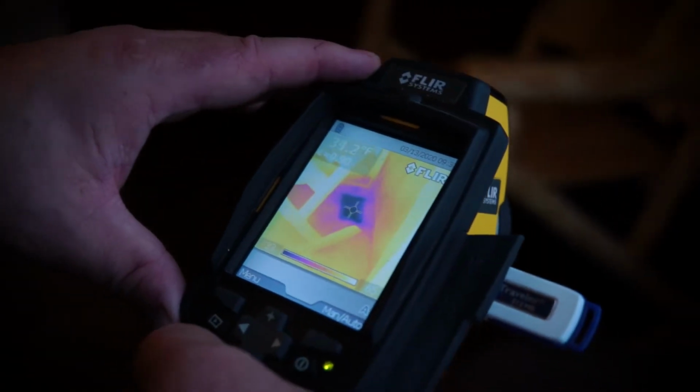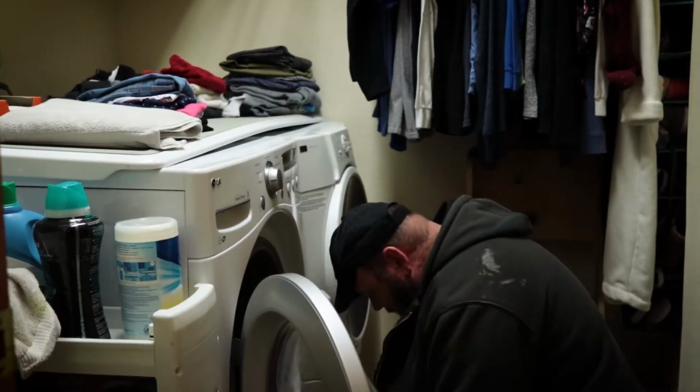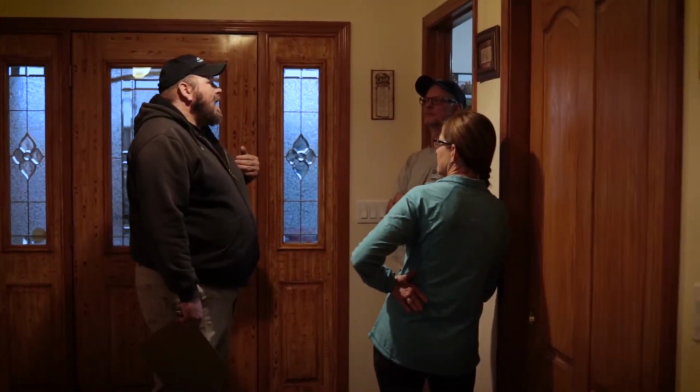So we're doing the blower door test. We're going to look at their attic insulation, their crawl space, their basement. We look at your appliances, your heater, your furnace. In fact, our auditor is interviewing the homeowner right now. We look back through the history of the permits, so we know ways to upgrade that automatically based on those standards. We're also looking at an interview on electronics, any abnormal usage or draws for electricity.